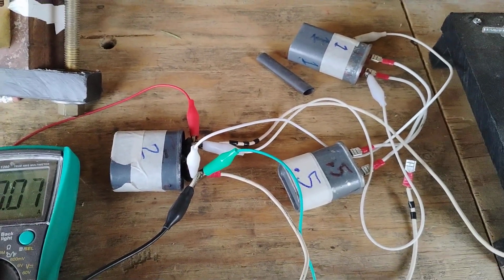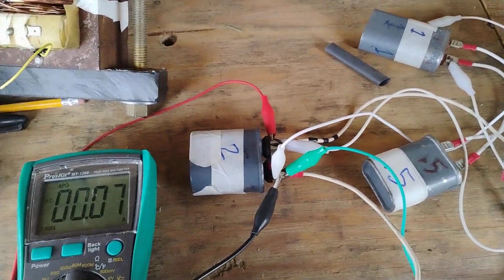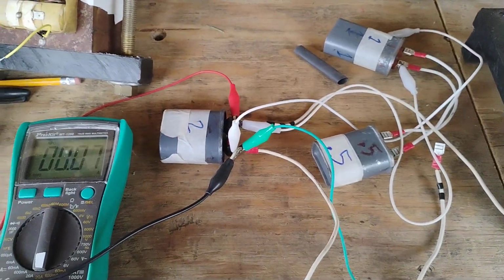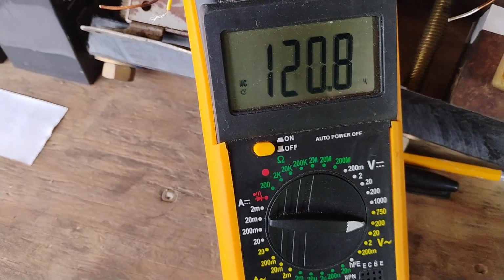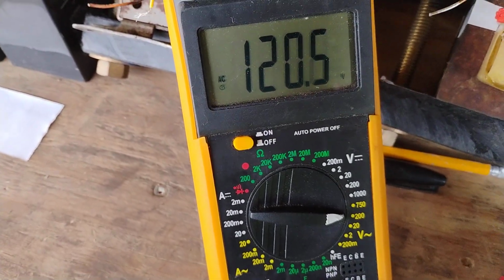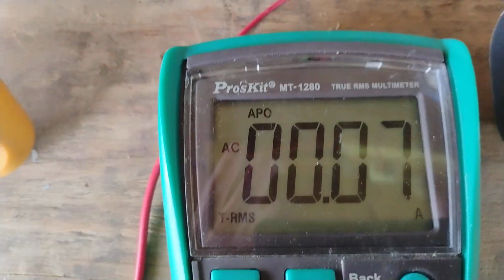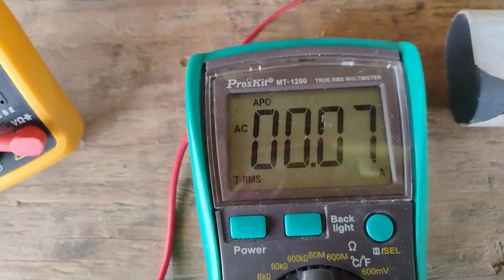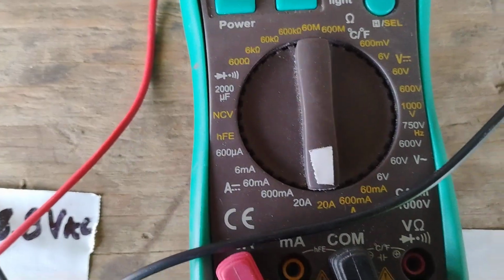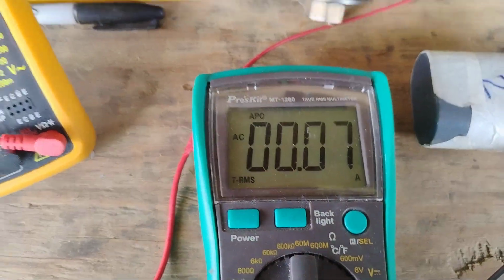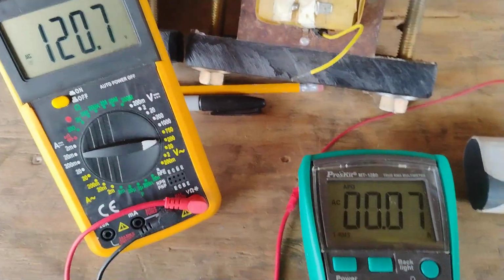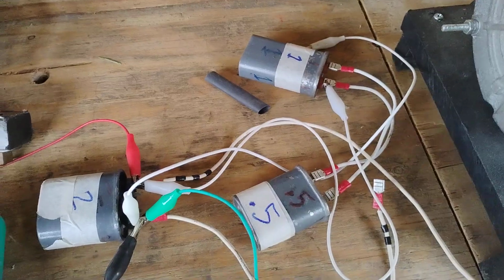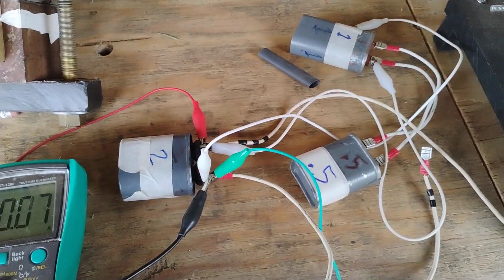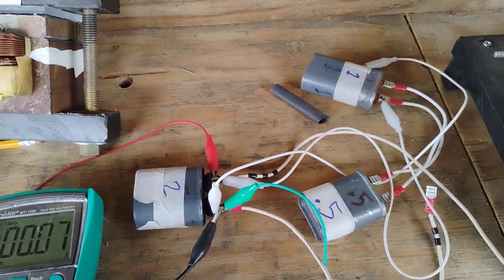Right now I have a 2 UF cap only on the run cap phase from L2 to L3. And I have 120 volts across the run cap phase, and 70 milliamps of current circulating. This is not watts, this is VARS circulating in the run cap phase, V-A-R-S.